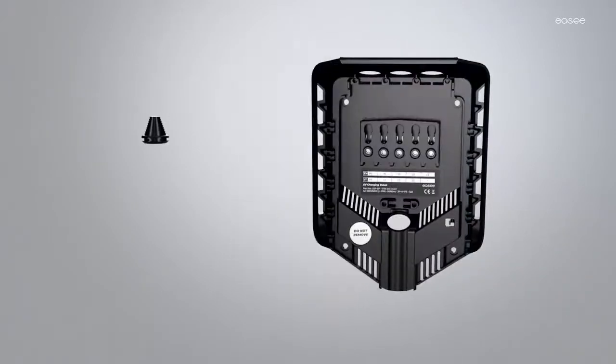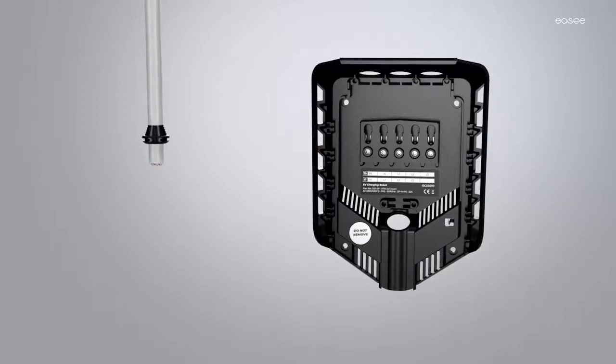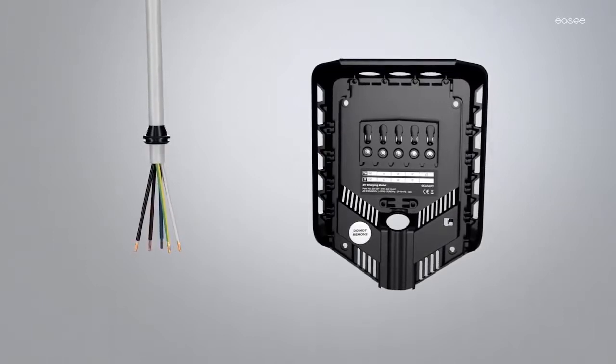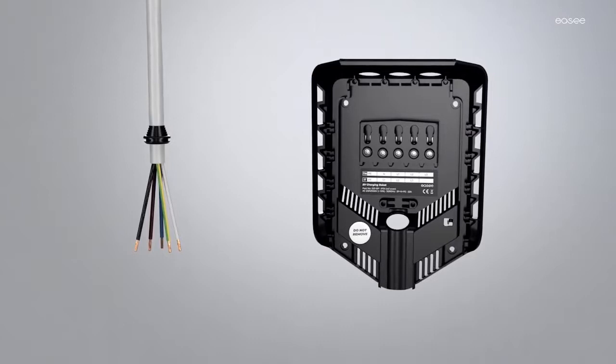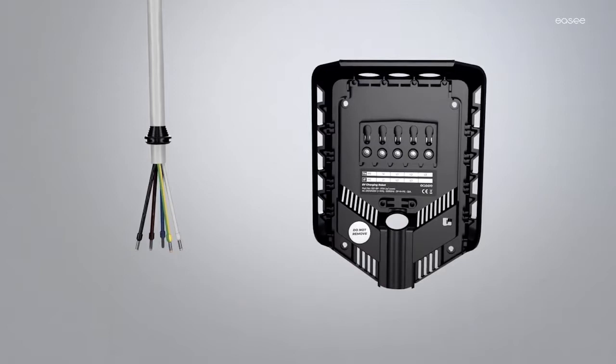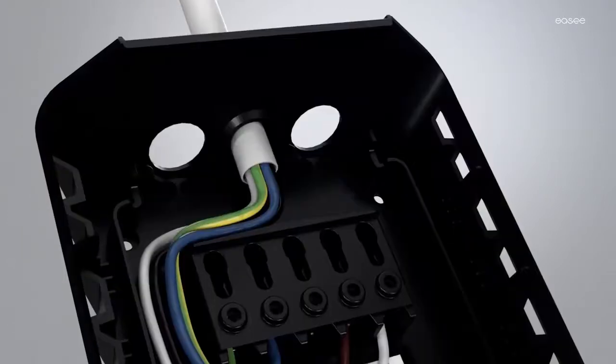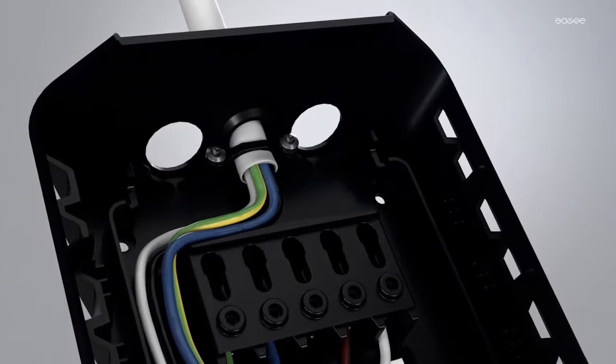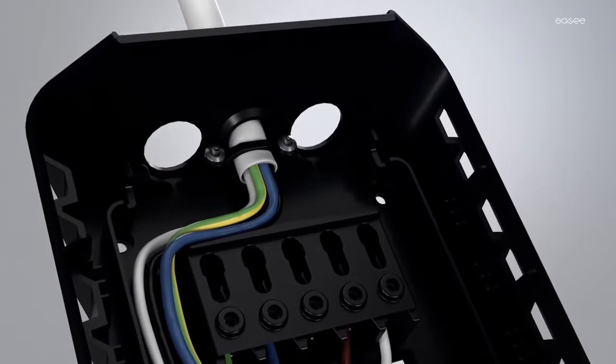Fit the sealing plug on the cable before connecting in the backplate. Strip back all cable cores allowing 12mm exposed conductor. When needed use cable end sleeves on all wires. Secure the sheath of the cable with a strain relief.